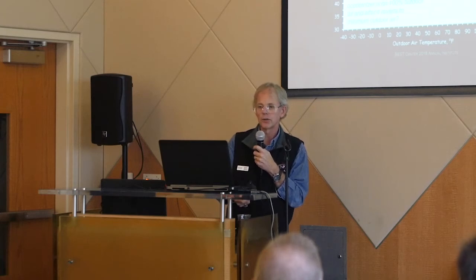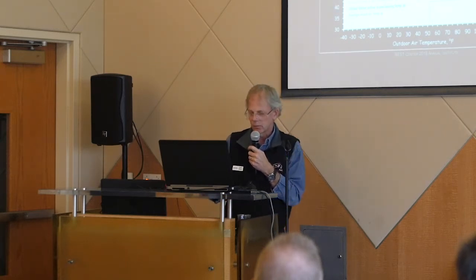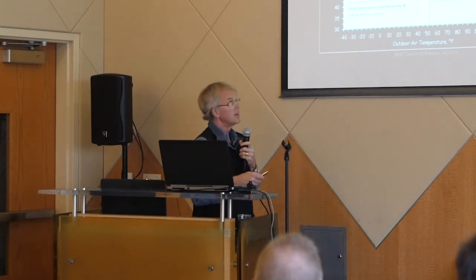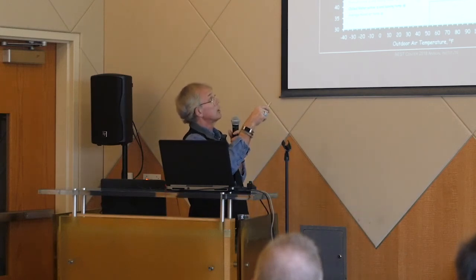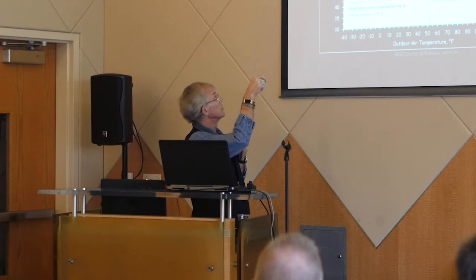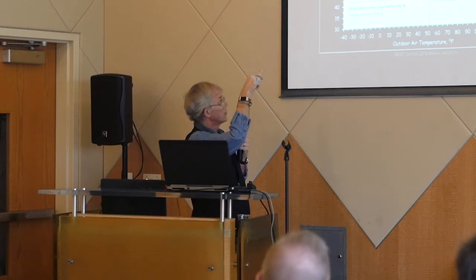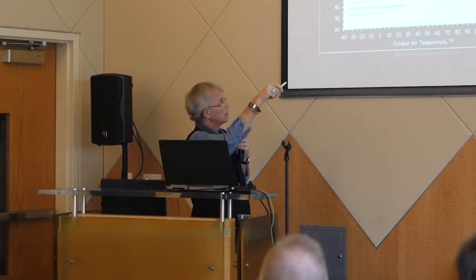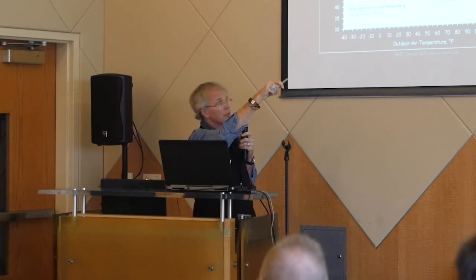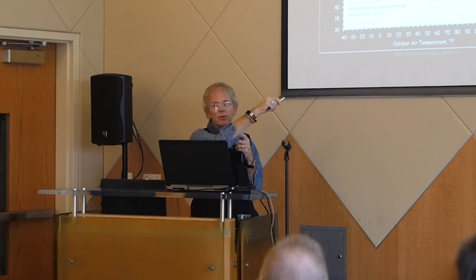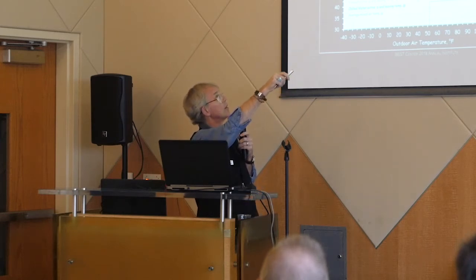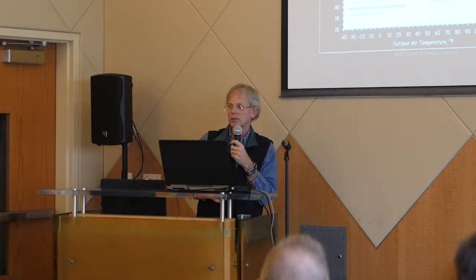So you can paint a picture of how that perfect economizer should work, and add some other stuff to help with diagnostics. That line means: if I had a perfect economizer and plotted outdoor air temperature versus mixed air or return air, depending on which you're looking at, all the data points would be right on that line. So if I take that line and plot the real data on top of it and get these clouds, that cloud is telling me about the dysfunction in the economizer, right?